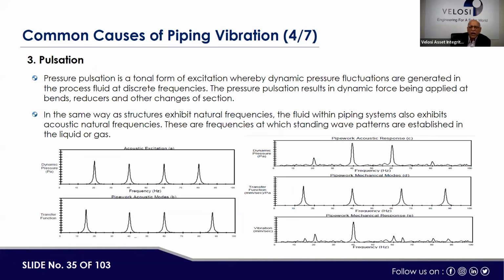How pulsation works: if we see that pistons are moving back and forth, right? There's a movement back and forth, and at some stage it is pushing the fluid forward, sometimes it's coming backward. And that pulsation is basically for positive displacement, piston-driven compressors or pumps. This issue is more connected with that. In the centrifugal type, mostly the centrifugal impeller is moving in one direction, so there are fewer chances of pulsation. But if the driver, like a pump or compressor, is a positive displacement piston-driven type, then pulsation could be the more dominant cause of the vibration.